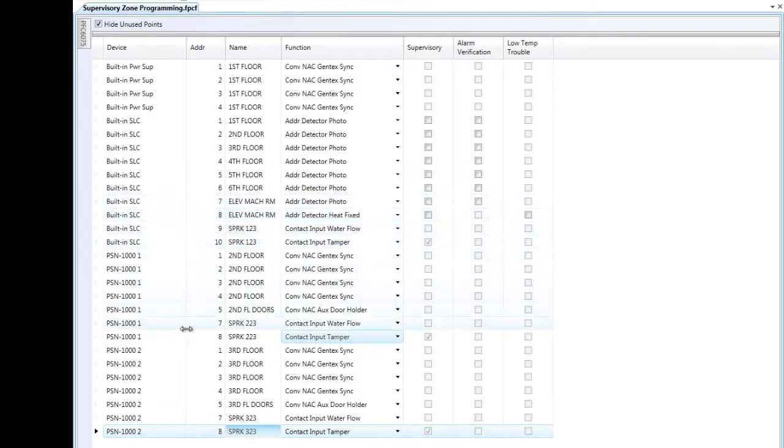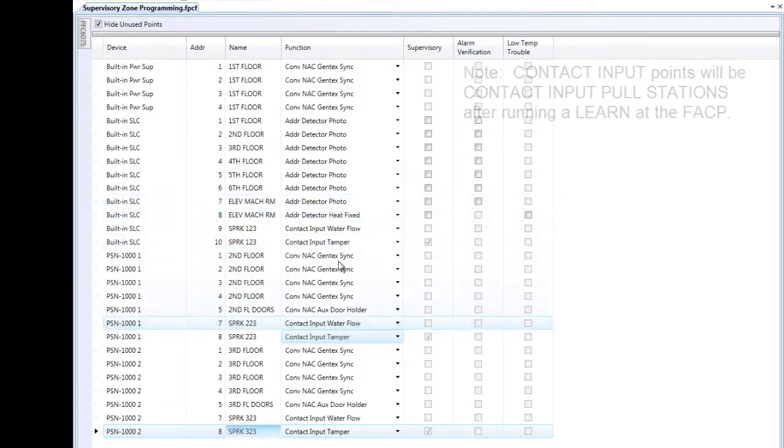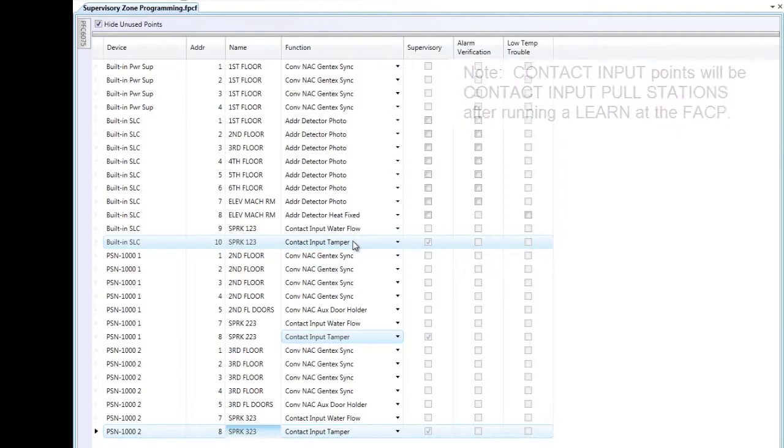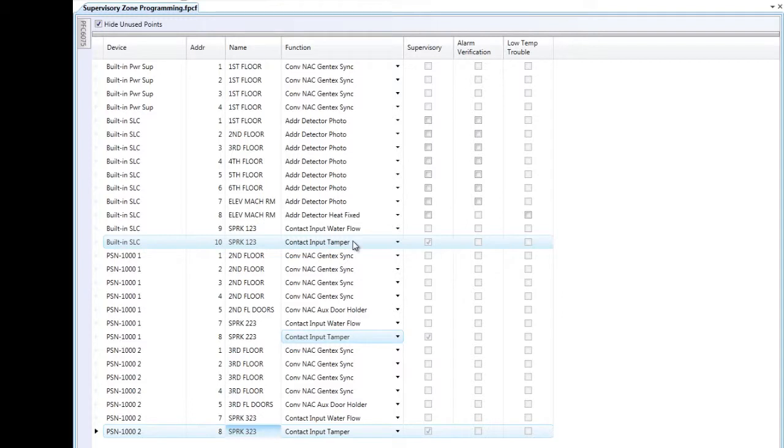When I did the upload, these points came in as contact input pull station. That is the default when you do the learn at the fire alarm control panel for any contact input point. So I have now changed them to a supervisory condition from an alarm condition.